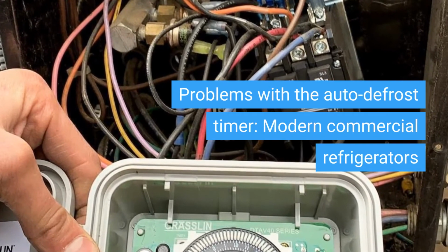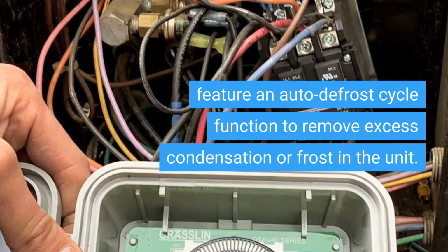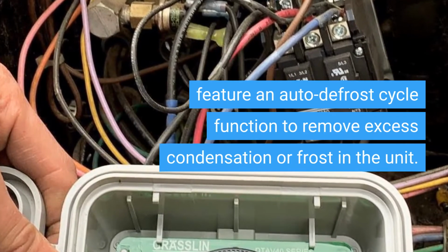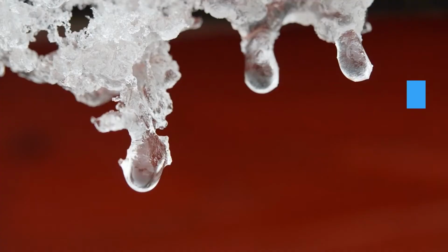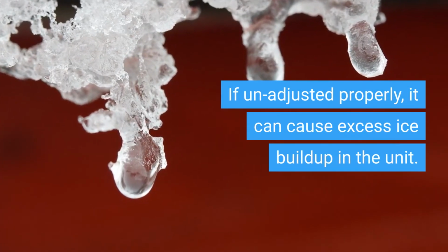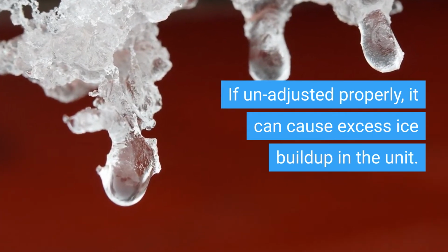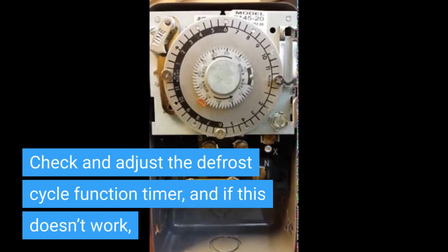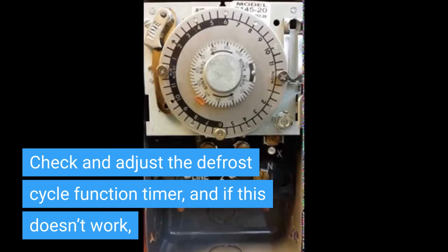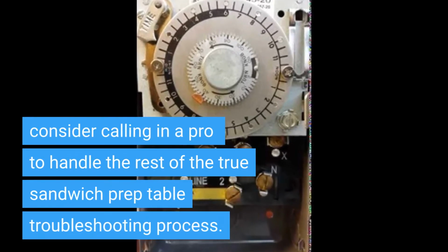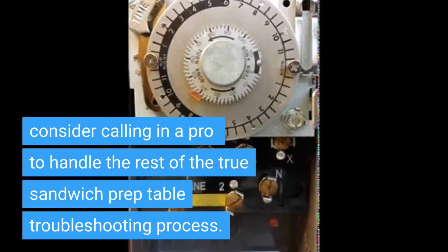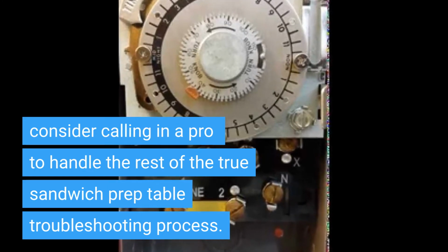Problems with the auto defrost timer. Modern commercial refrigerators feature an auto defrost cycle function to remove excess condensation or frost in the unit. If unadjusted properly, it can cause excess ice buildup in the unit. Check and adjust the defrost cycle function timer, and if this doesn't work, consider calling in a pro to handle the rest of the true sandwich prep table troubleshooting process.